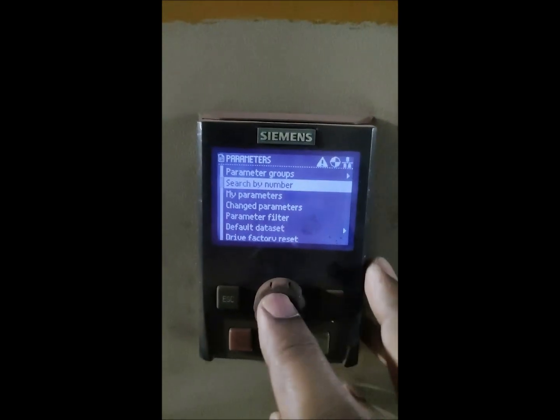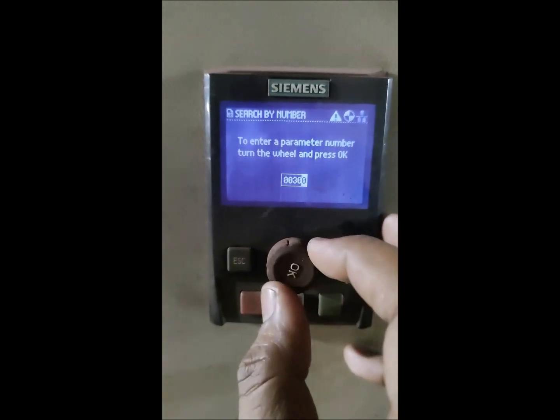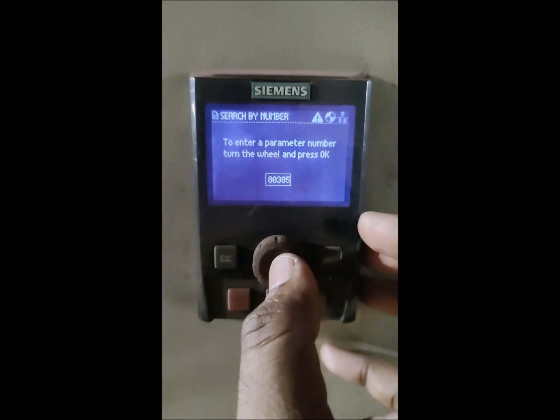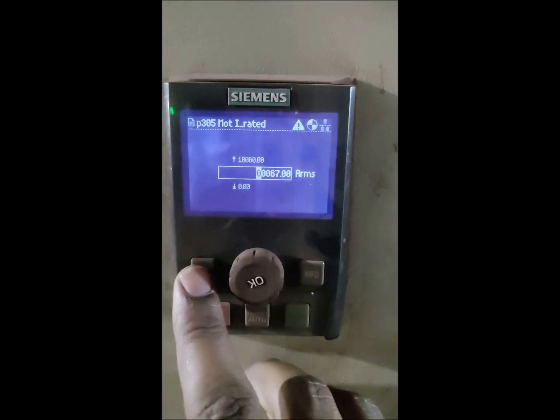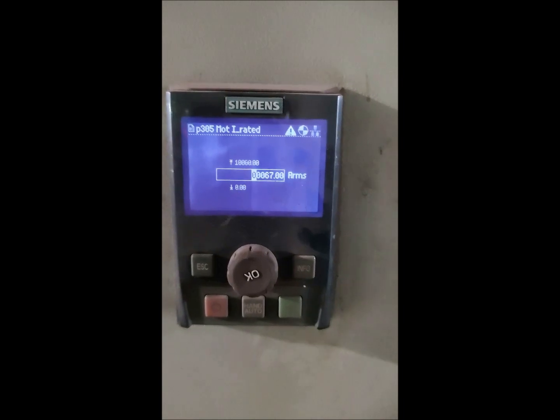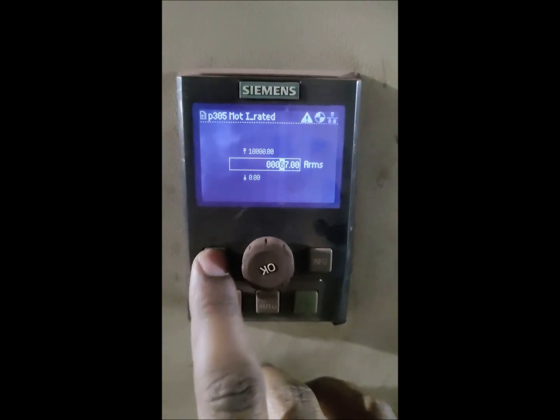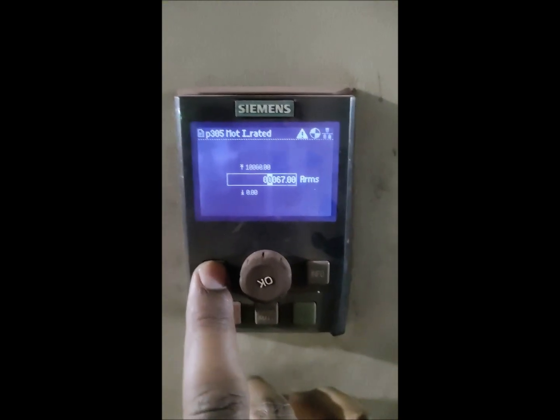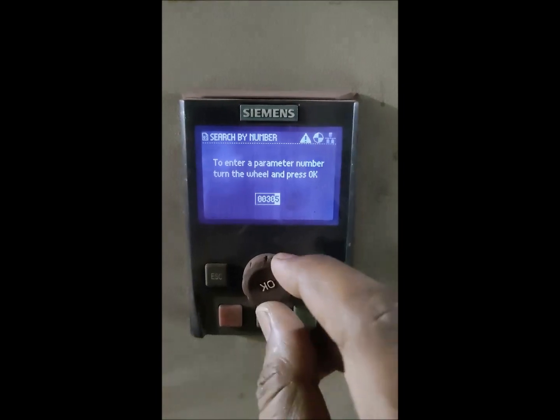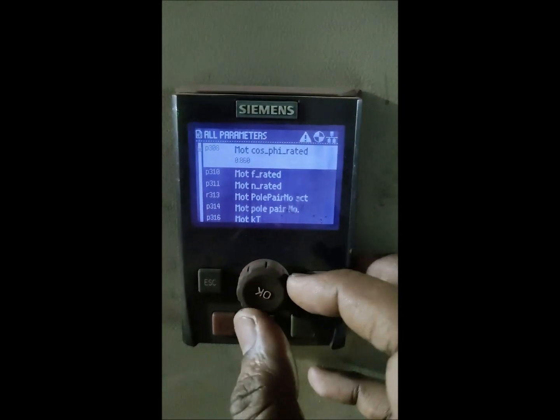We go to parameters and search by number - that is the best way. We will directly go to 305 to check the current. Earlier, after factory reset, the current was 477 and the power was 250. Now you can see the current is 67. So the drive has been successfully factory reset and we have successfully downloaded the program from the healthy drive, which was of 67 amps. Likewise you can check all the other parameters - you can edit them. There is a separate video on how to do all these things and what are the important changes you need to make, like voltage, current, power and all such things.